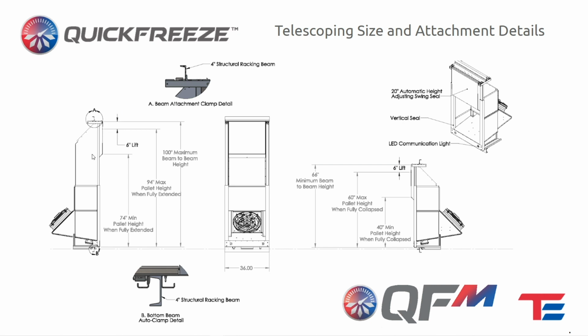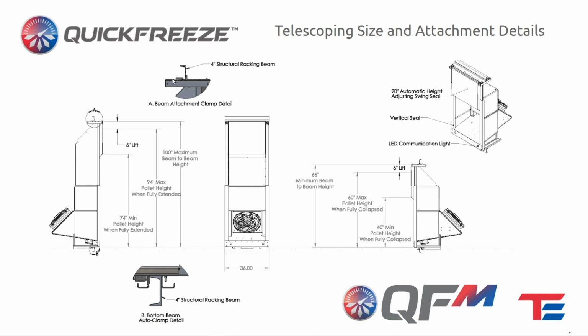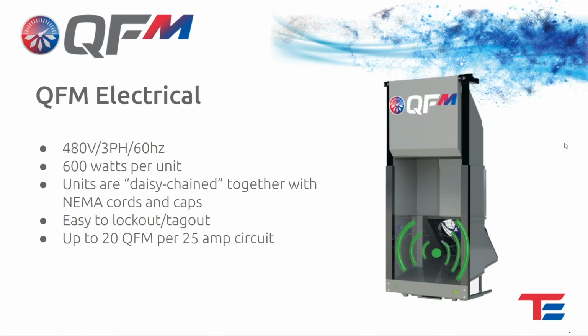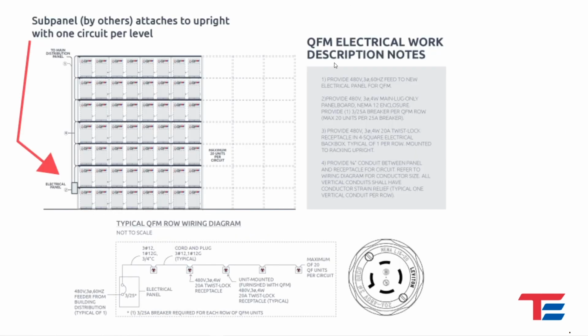This is a detail sheet kind of showing the different views of the units. As you can see down in the lower corner here, this is how that bottom beam attaches. The unit actually sits down on it, has a spring-loaded keeper. Then the top beam, the unit is extended up, pushed up to that top beam, and then those back attachment clamps are actually drawn up and seated at the back of the top beam, securing that in place so the pallets can be pushed up into the position there. Electrically, the units require 480 3 phase, and they're under an amp per unit, and again, daisy chain one to the next, up to 20 units on a 25 amp circuit, which makes it easy to service these as well as install.